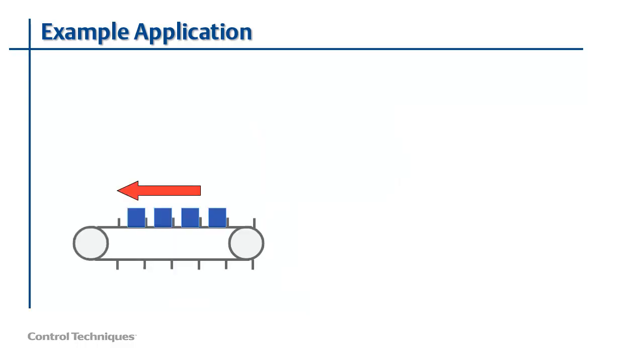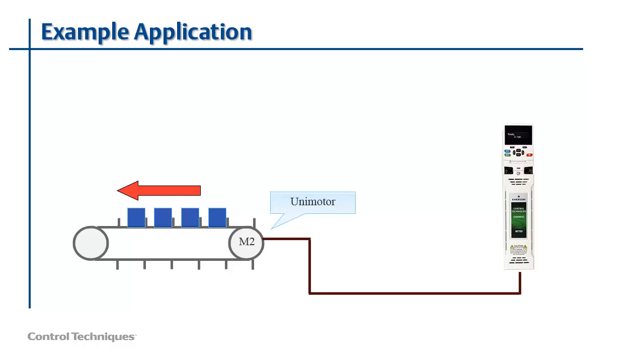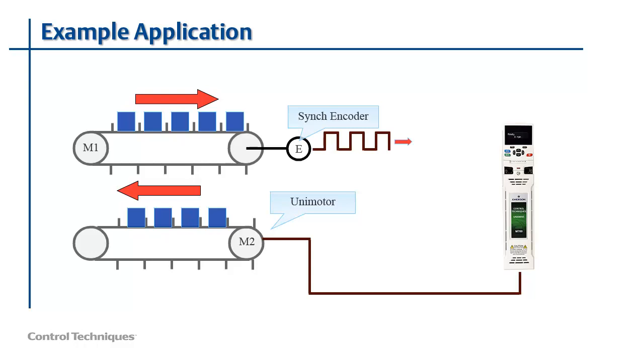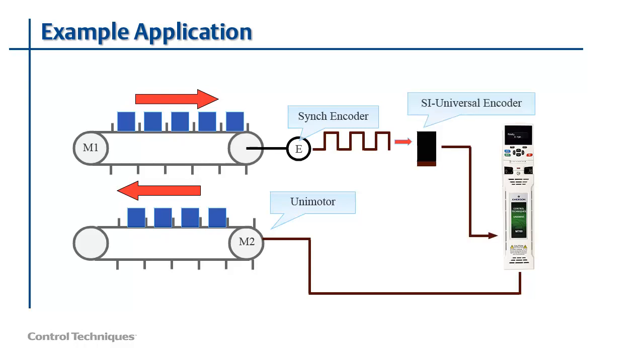To solve this challenge, we'll begin by using a Unidrive M700 and a Unimotor permanent magnet servo motor to operate the lower conveyor. Next, we'll couple an encoder to the top conveyor. This encoder will provide a speed reference for the Unidrive M700 to follow. There are a couple different ways to integrate a secondary encoder into the Unidrive M700. One way is to wire the encoder into the encoder port on the drive. This method depends on the encoder you've chosen for your primary motor feedback. If you're using a serial-only encoder, such as an EnDat encoder, then you're able to wire the secondary encoder into the same connector on the drive. The other option, and the one I'm going to be showing you in the video, is to add an SI universal encoder module to the Unidrive M700 and wire the encoder into it instead of the drive.